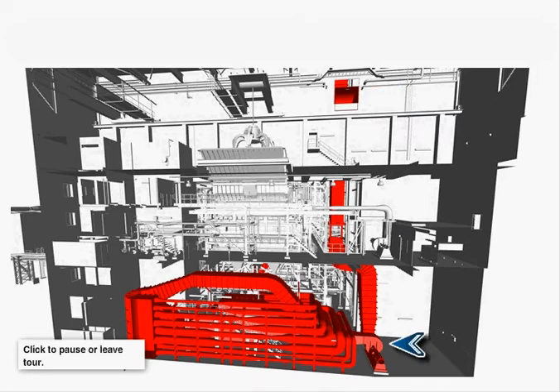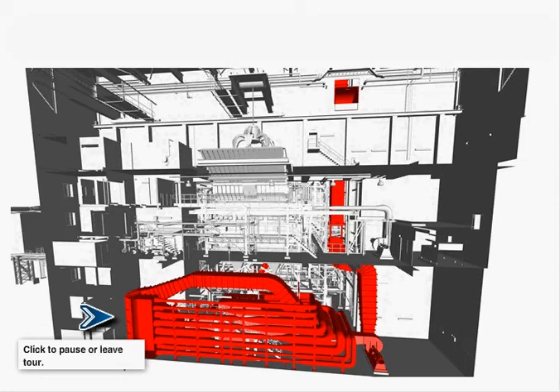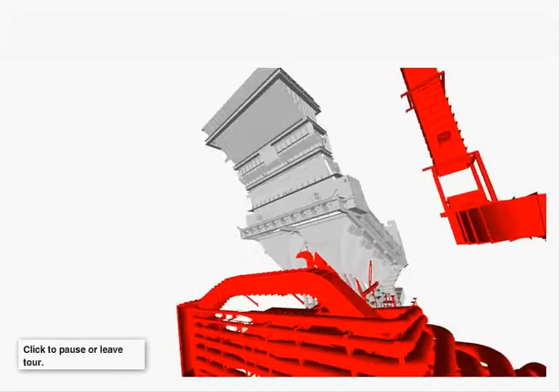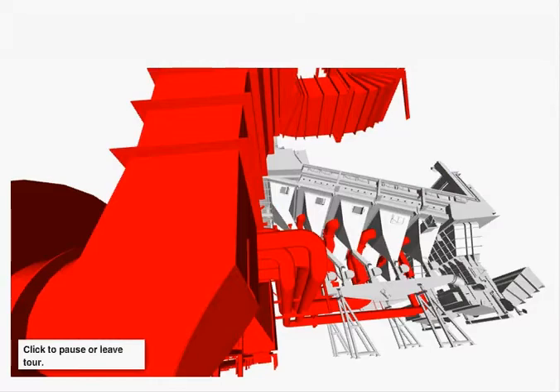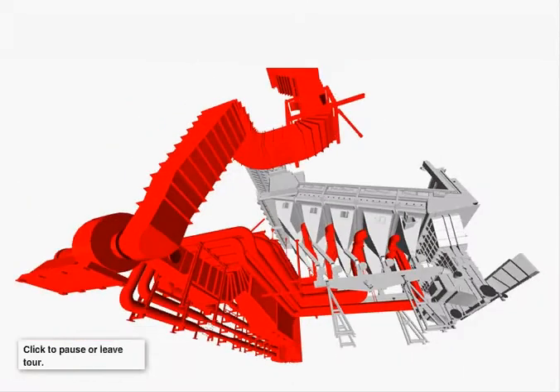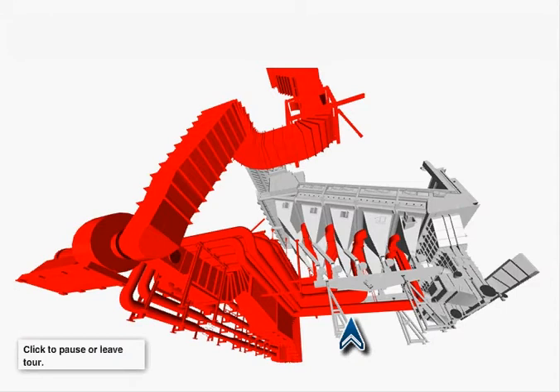The combustion air fan provides the flow into the air manifold. In order to control the air flow in each individual combustion section, the flow will be measured by the Venturi system. The primary air is distributed under the grate into the individual combustion sections. In order to enhance the combustion process, the primary air is preheated up to 150 degrees Celsius.